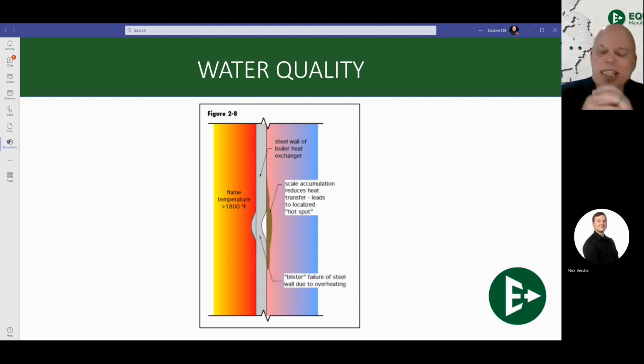Here's a visual representation of exactly what's happening and why we crack heat exchangers. We get the buildup, as you see there on the right-hand side of this picture, the buildup of this scale is going to be inhibiting the scrubbing of heat away from our flame. Our flame's over here, you know, we're burning natural gas. The flame temperature is sitting there at around 1800 degrees, probably closer to 2000, but let's just say it's 1800 degrees. The water needs to move through on the other side of that heat exchanger to scrub that heat away. At 1800 degrees, it does not take long to warp and damage metal. I don't care if it's stainless, I don't care if it's aluminum, I don't care what it is. It doesn't take long to warp metal at those sorts of temperatures.